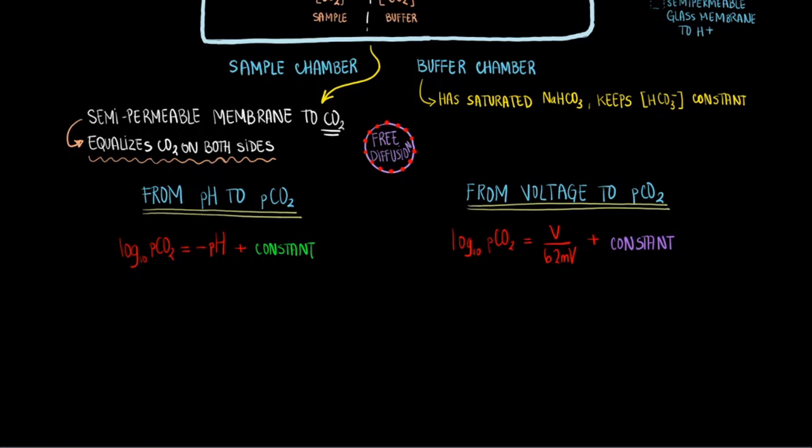Once again, this constant can be measured in a single step during your calibration with a sample of known PCO2. Keep in mind these constants could also vary with time.